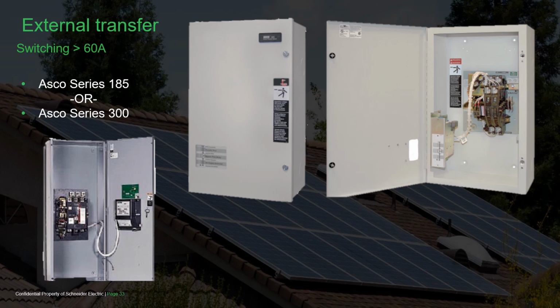When installing an automatic transfer switch to solve the 60 amp pass-through, there are several off-the-shelf solutions that may be used, including Generac. Many customers choose the ASCO transfer switch because they are cost-effective and reliable. The fact that they are Schneider Electric is an added value. The Series 185 is the most basic model that lacks the programmability for specialized applications. When switching may need to be prioritized in a manner that is more complex, the Series 300 provides greater flexibility.